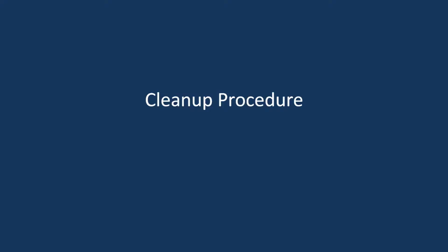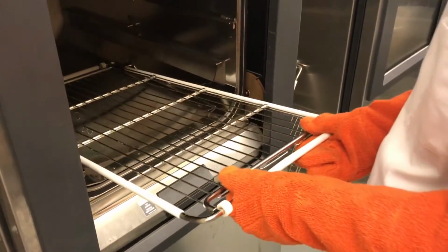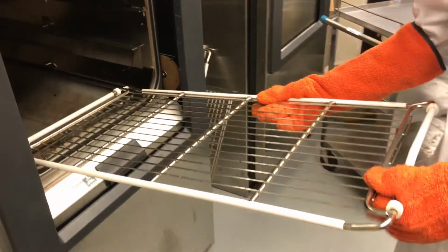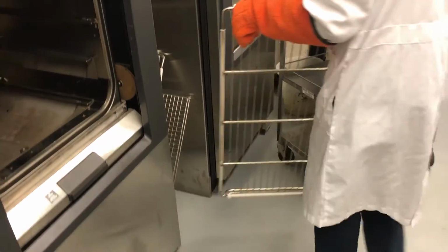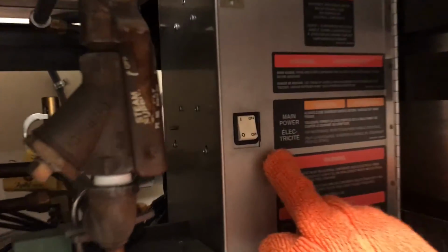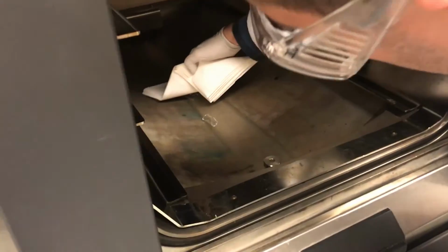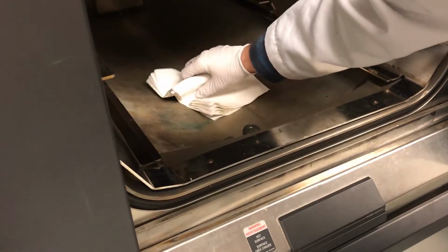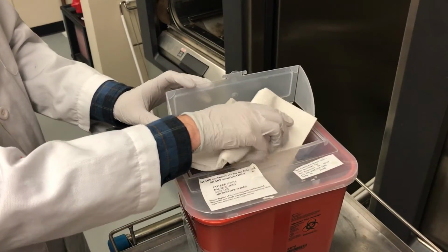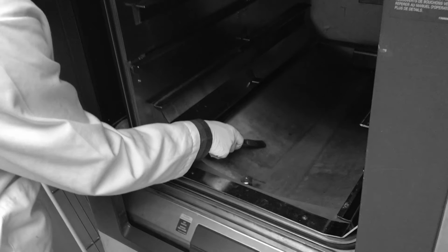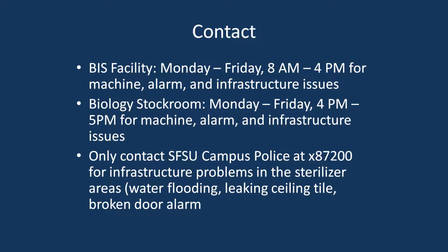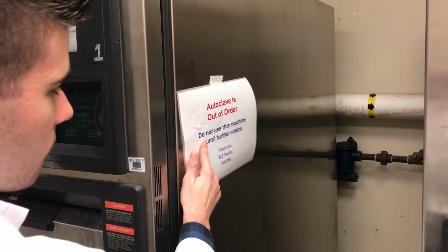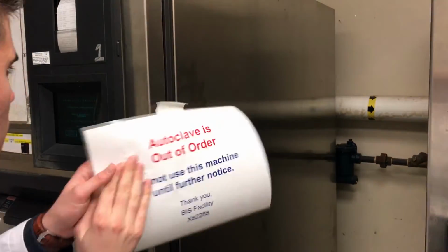Cleanup procedure. First, open the autoclave door. Remove all items, including the autoclave rack, from the autoclave chamber. Next, turn the autoclave power switch to the off position. Allow for it to cool, and then use paper towels and water to clean up the mess. Do not use any sharp tool to scrape the inside of the chamber. Next, notify the BIS facility via phone and/or email. Finally, place an out of order sign on the screen of the autoclave.